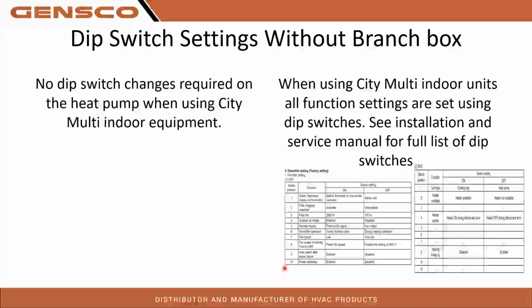Dip switch settings without branch box. On the heat pump, there are no dip switches that need to be changed. So the SW25 switch will stay off because you don't have a branch box. If you turn that switch on and you're using city multi indoor equipment, so you don't have a branch box, it is going to give you an error code, and it's going to be for incompatible equipment combination because you're telling it there's a branch box in the system when there's not, and there shouldn't be. So if you see that, that's why. Check your SW25 with city multi equipment, make sure that it is turned off.